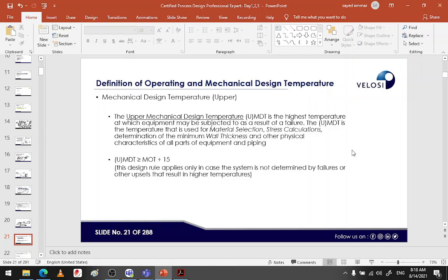You got me or not? To be honest, not really. That's what I love. One question to make it more clear. Most companies use the credible scenario for the maximum temperature and the corresponding maximum pressure, or they use the worst case for each parameter. Which company are you speaking about? Operation company? Generally, different companies design equipment for the credible scenario for the maximum pressure and corresponding temperature, or they use the worst case in each to design equipment.